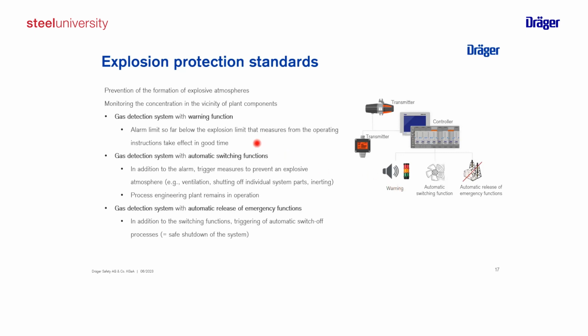The second step is using automatic switch functions. That means the control system will activate ventilation or will close any kind of the process, but the process itself will stay in operation. And the last is what we call emergency functions. So in this case, the process will be shut off and only systems which are relevant for the emergency and to keep a safe state are kept in operation. So we see a gas detection system can have a big impact on your process, but also on your safety.